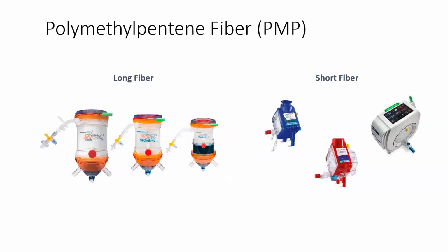I bring this up, polymethylpentene, because polymethylpentene fiber is what the current oxygenators are made out of, and this technology is one of the reasons that led to the propagation of ECMO throughout the world. There's two different styles of these fibers. You have long fiber, which are over here on the left side. These are Eurosets. These are wound around a heater coil. They are longer fibers. They're higher resistance membranes. They're not going to last as long as the ones on the right, which are short fiber.